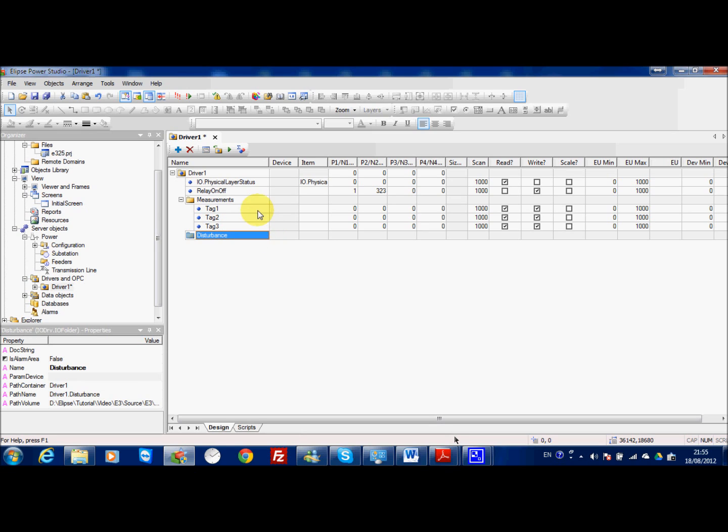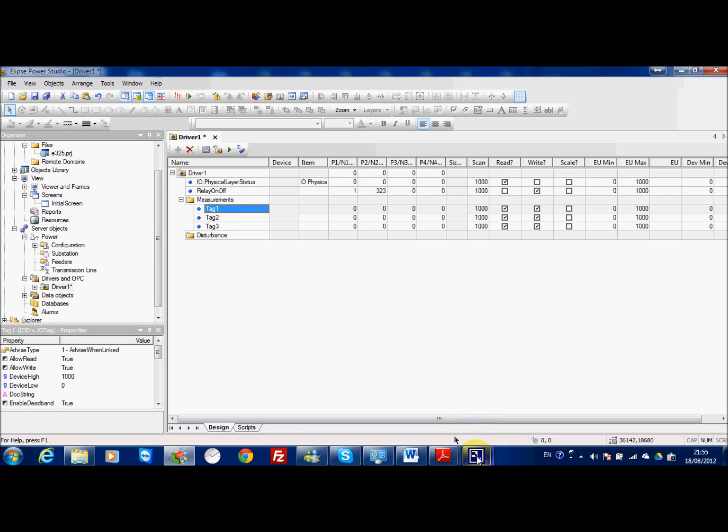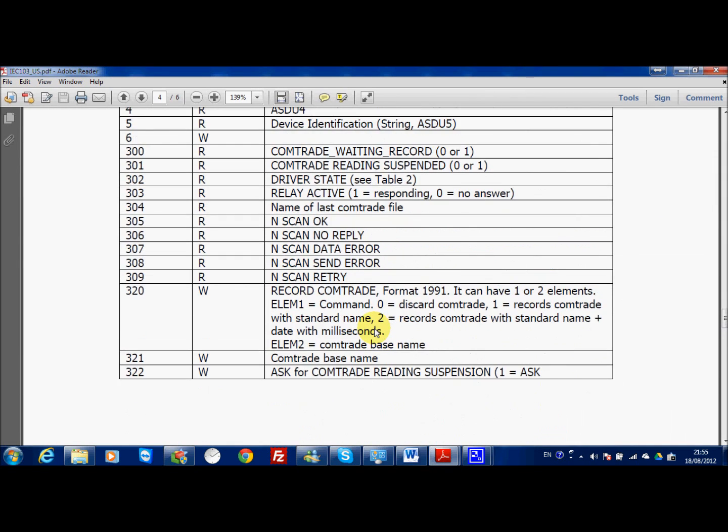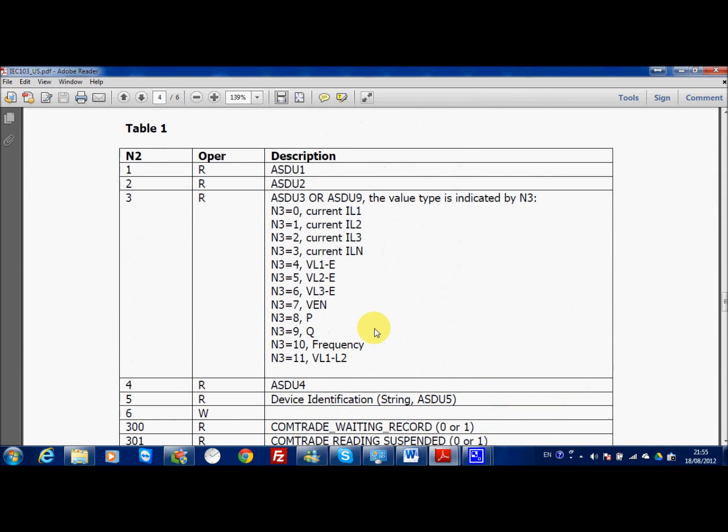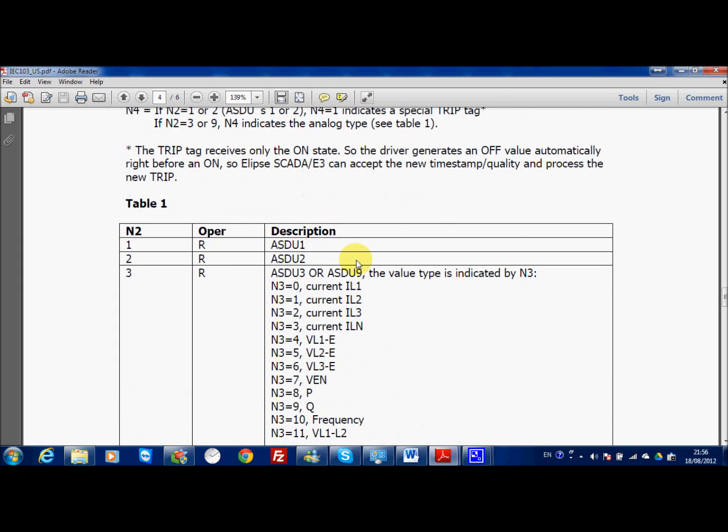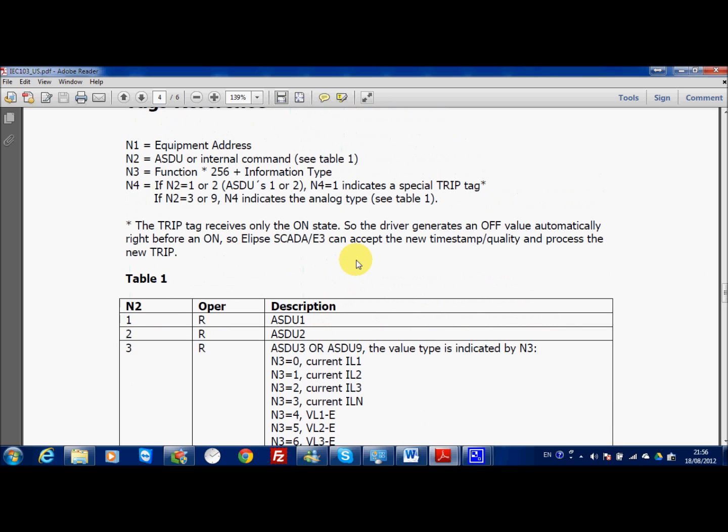For the tags you need to implement different kinds of tags according to the data type of your tag. Here you will find all information you need for the ASDU. You can use ASDU3 or ASDU9 and then you have to also write the information for the function. The function multiplied by 256 plus information type will give you the correct information for the data type.